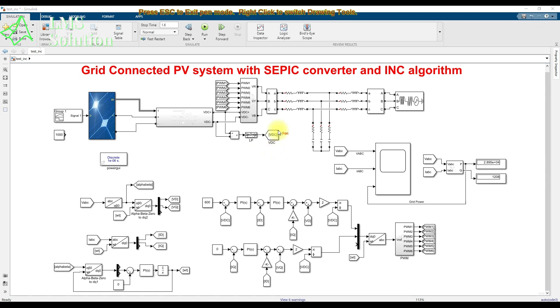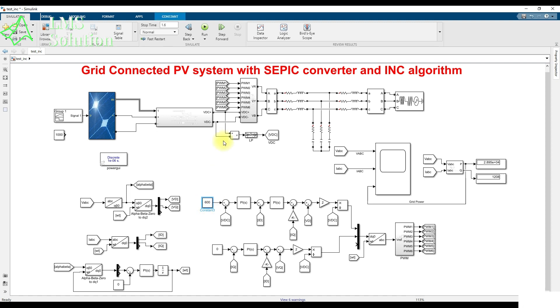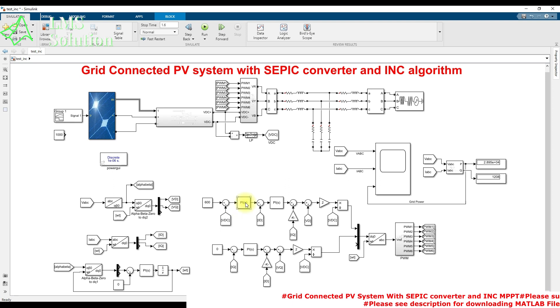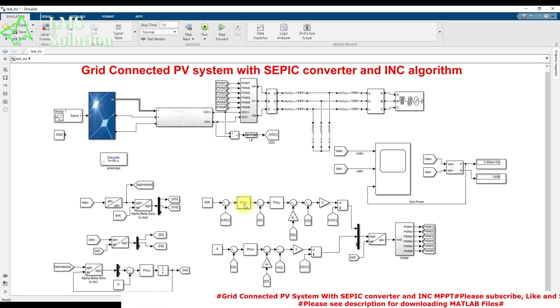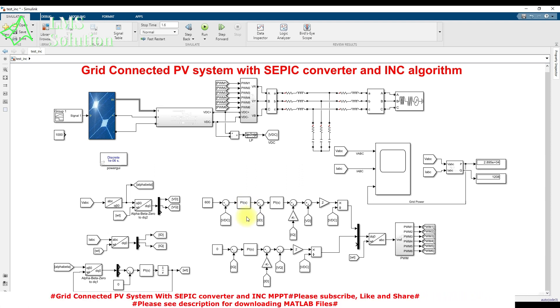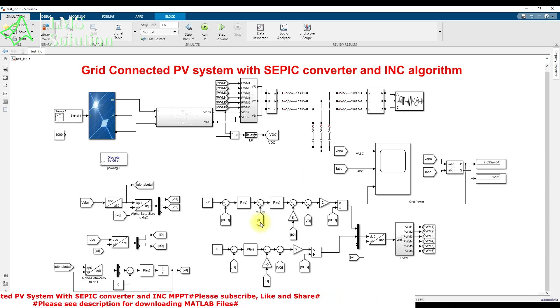For the inverter control, we measure the DC link voltage — the output voltage of the SEPIC converter — and compare it with the reference voltage of 600 volts. The error is processed through a PI controller, whose output is considered as the ID reference. This ID reference is compared with the actual ID of the grid current.